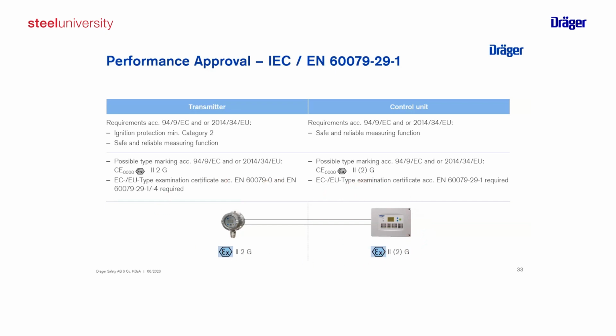And that is a requirement if we talk about primary explosion protection for the 29-1, that not only the detector is tested and approved, but also your control system, because you need to secure that the signals the sensor is providing are correctly understood and interpreted by the control system. And what you will find then, if this control system, what we call a kind of associated equipment, can be connected to a device in the field, but is not intended to be used in a hazardous area, you will find, especially in Europe, a marking on it that indicates that it is allowed to be connected to a device in explosive atmosphere, but is not intended to be installed there.